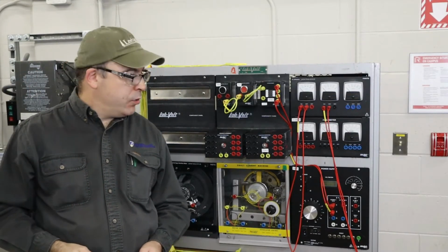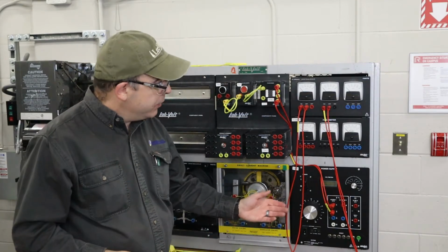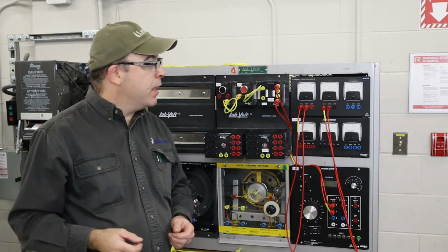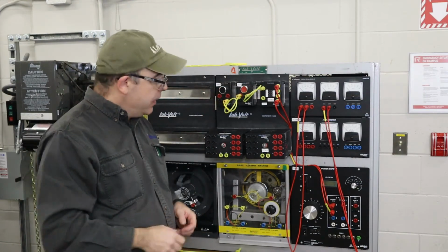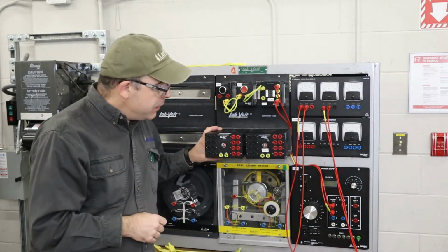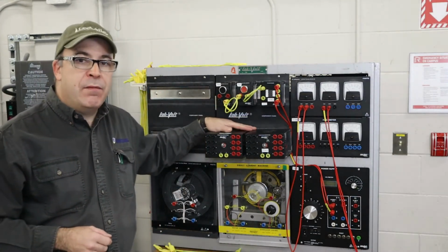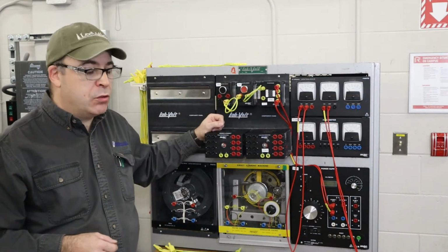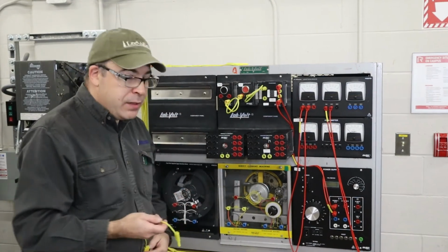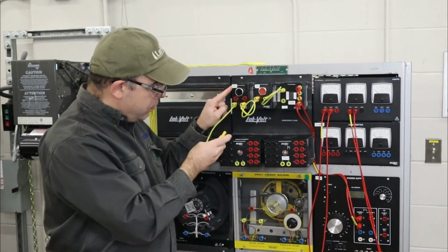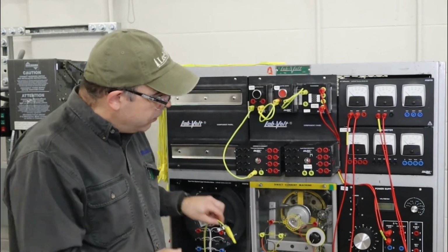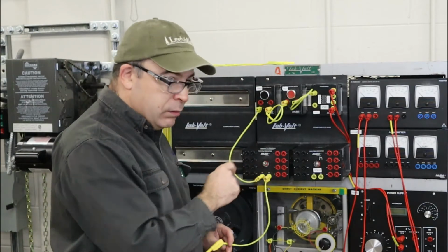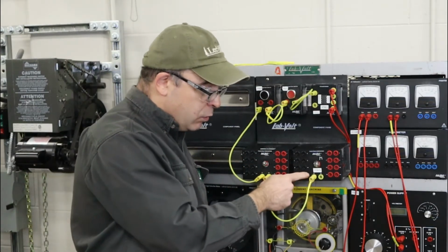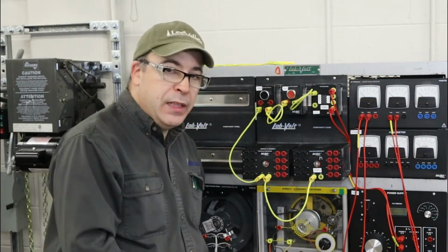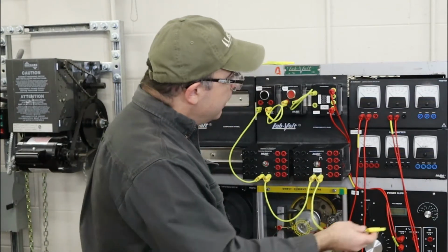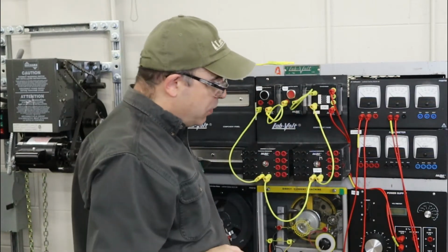Now here we are at the workstation, and I've already got the power supply pre-wired. I have a control transformer as per our diagram, a stop and start push button, and here I've got the 2 contactors. Now these contactors require 120 volts, which we're going to get from the control transformer. And to complete the circuit, what we're going to do is wire the start push button into the coil of the first contactor, out of the coil of the first contactor into the coil of the second contactor, and then I'm going to complete the circuit and going to X2 of the transformer.